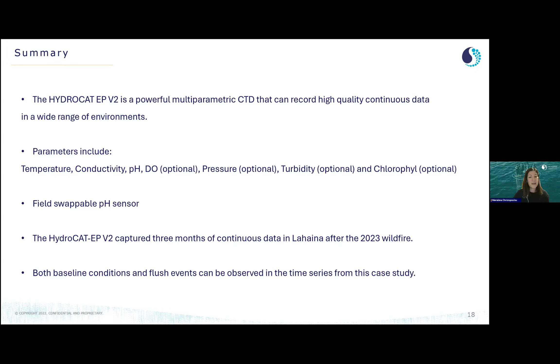To summarize our findings and today's talk, the HydroCAT-EP V2 is a powerful multiparametric CTD that can record high-quality continuous data in a wide range of environments. Parameters that can be measured include temperature, conductivity, pH, dissolved oxygen optional, pressure, turbidity, and chlorophyll also optional. It is equipped with a field swappable pH sensor. The HydroCAT-EP V2 was used to monitor the water quality after the Lahaina wildfire in Lahaina and capture 3 months of continuous data. Both baseline conditions and flush events, short-term events, can be observed in the time series that were created from this case study.